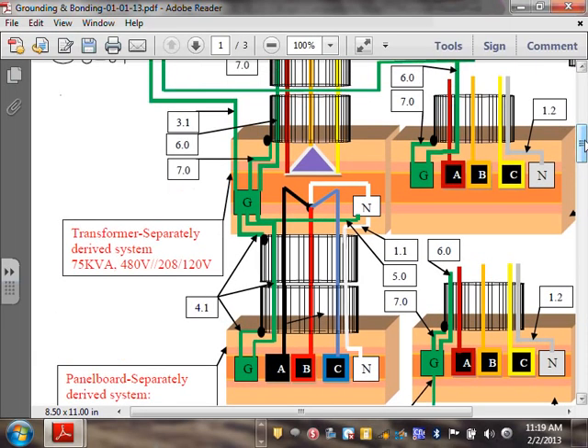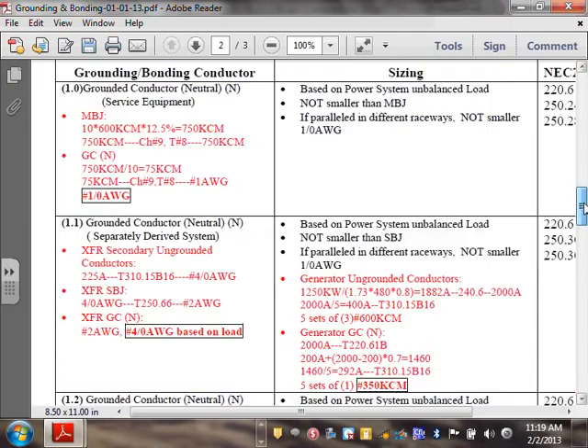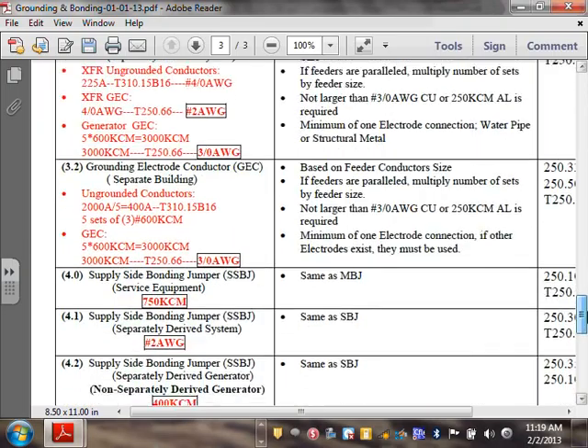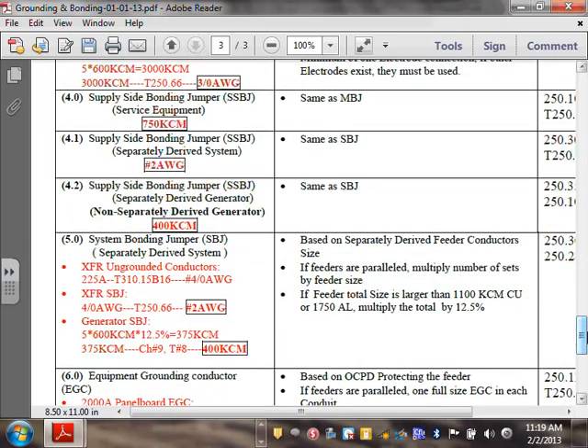So let's go to the neutral. We bonded the neutral. Now I'm coming here. I call this number 5, guys. It's really a main bonding jumper, except to distinguish it from the service, they call it system bonding jumper. For all practical reasons, the way they size it, it is exactly like a main bonding jumper, except the name is different. Okay, so system bonding jumper. And can you guys see that little conductor number 7 here? Let's just look at number 5. If you go to number 5, all the way down, that's called what? System bonding jumper. Okay, here's my system bonding jumper.